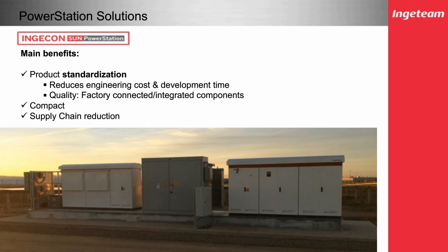And further advantages, from what I've shown previously about connecting multiple inverters to a single low voltage winding, what we call the power station design, offers a compact solution integrating onto a skid a complete solution of the DC connection and the AC output of the step-up transformer in a more plug-and-play way.